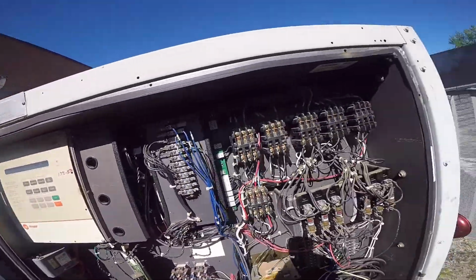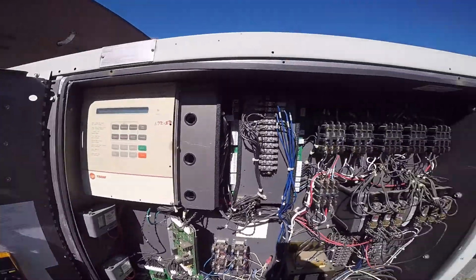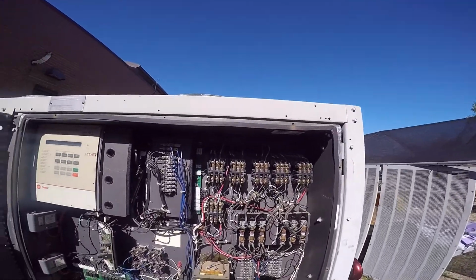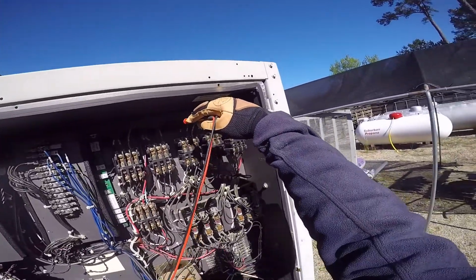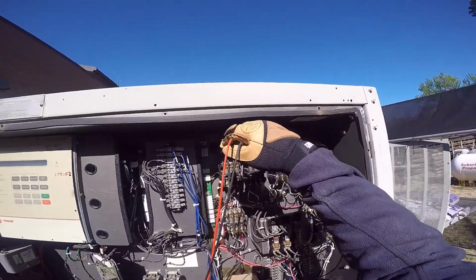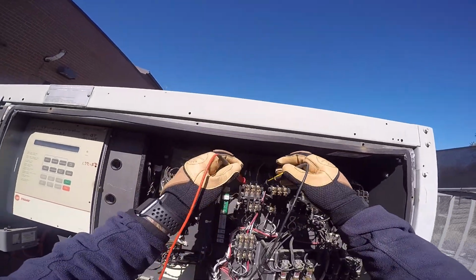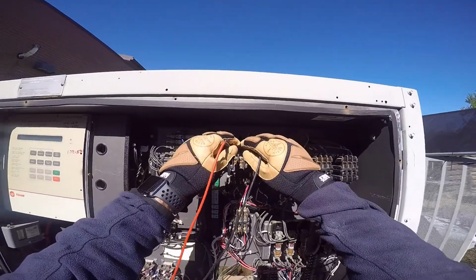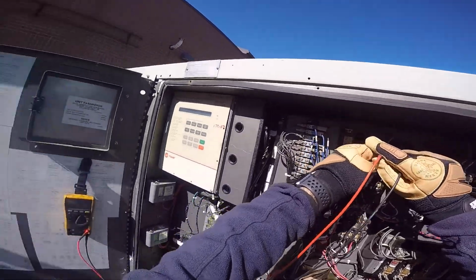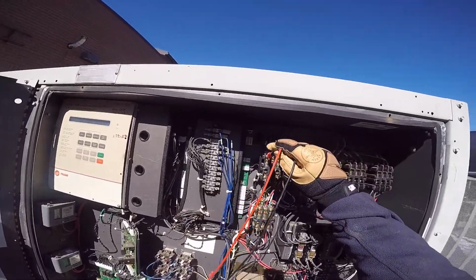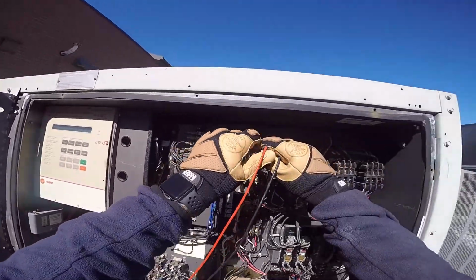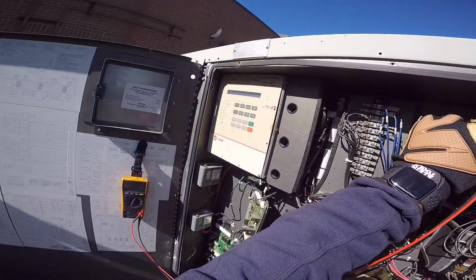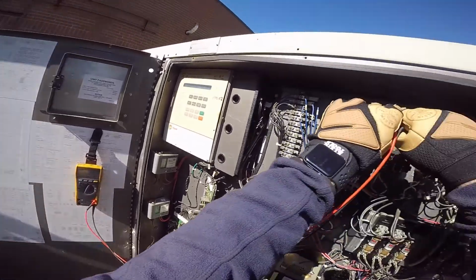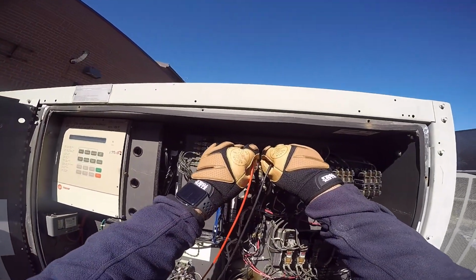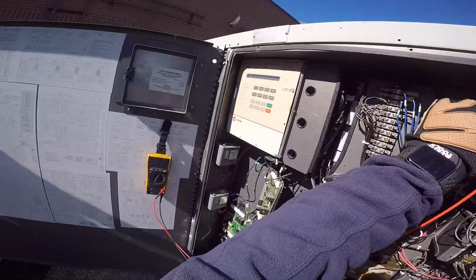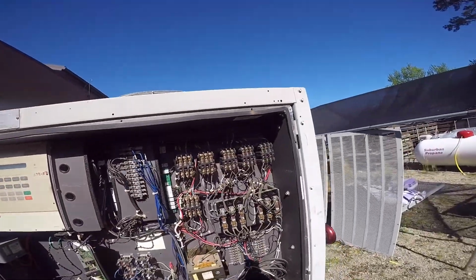Now on these contactors, when I've only got one fan motor per contactor, as we could see here, I could come to the top of the contactor. There's no power because the unit's not running. There's power to the system. I can ohm that out there. So 1 to 3 is 3.3 ohms. Now I'm going to go 2 to 3, and I'm looking for, and I've got it, 3.3 ohms again. And now I just do 1 to 2. I'm looking for 3.3 ohms again, and I got it. Okay, that's all you're looking for.